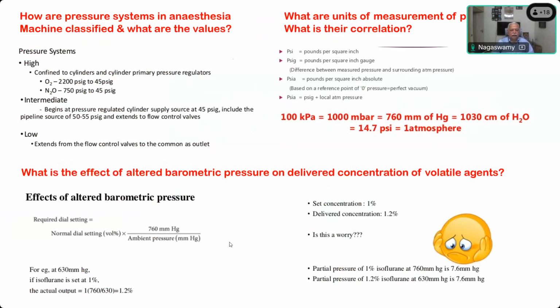So the dial setting need not be altered to suit higher altitude, even though the concentration output will be more, because the ambient pressure is low. The partial pressure of the volatile agent is the one which determines the uptake, so it will be the same. If the examiner asks whether you need a different type of vaporizer for higher altitudes like Kodaikanal or Ooty where anesthesia is given, it's not necessary. You can use the same vaporizer that you use at sea level. Is the point clear? Yes, sir. So even though the output concentration by percentage increases, the partial pressure will remain the same because of the lower ambient pressure there.